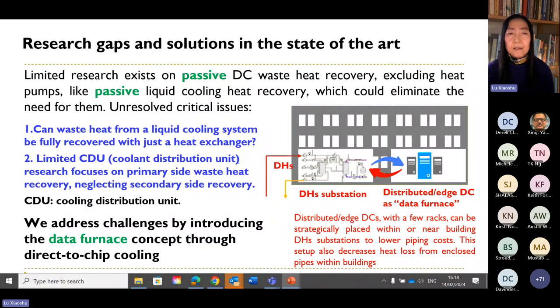To solve these problems, we introduce a new concept called data furnace through direct-to-chip cooling. The concept is illustrated in the graph on the right-hand side that involves placing a distributed or edge data center with a few racks as a data furnace within or near building district heating substations. Here you can see that a few racks can directly heat the buildings as a data furnace. This way, piping cost and heat loss can be minimized within a building. I want to emphasize that one of the aims of our invention is to simplify piping engineering work at a very low cost.